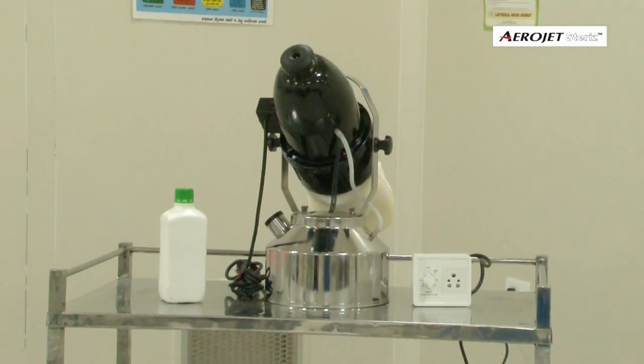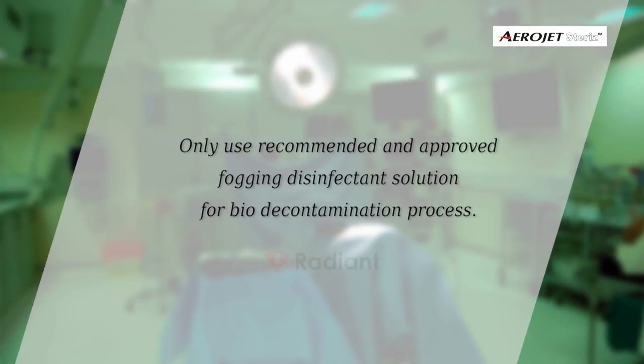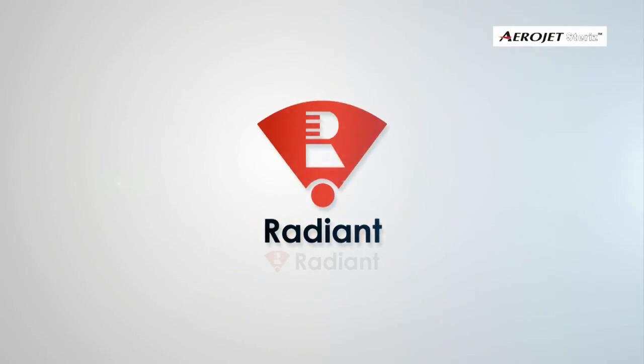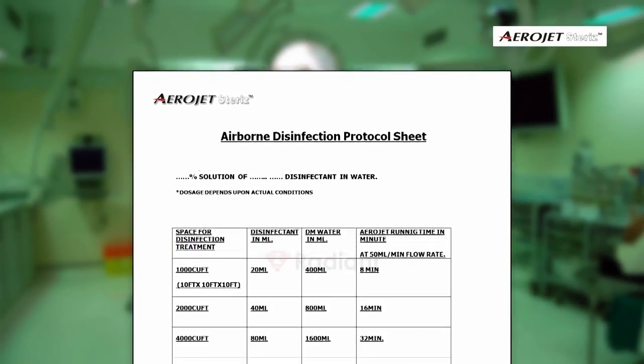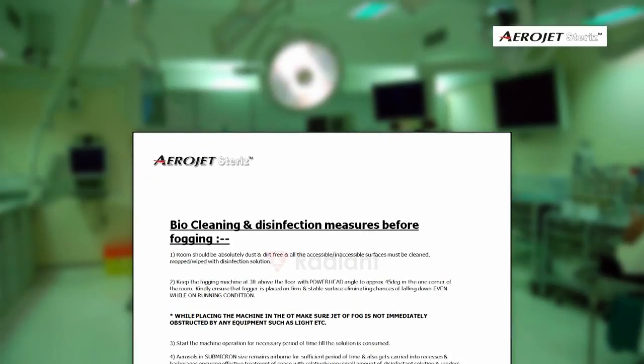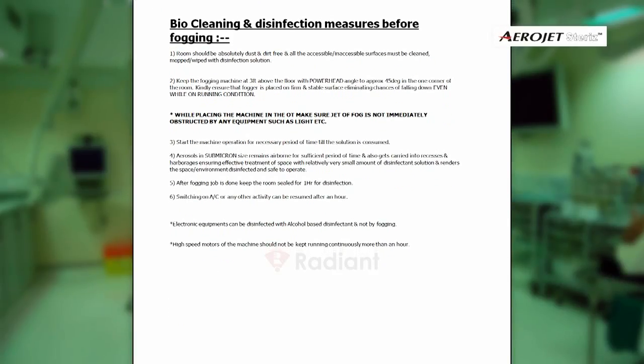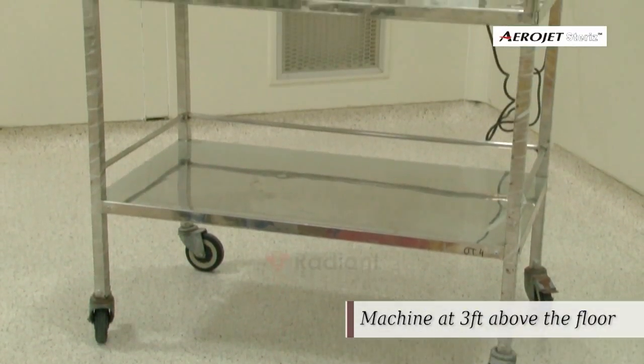Our machines can be used with many leading environmental disinfectant formulations and brands. Only use recommended and approved fogging disinfectant solution for the bio-decontamination process. Contact Radiant Enterprise for better understanding and guidance.